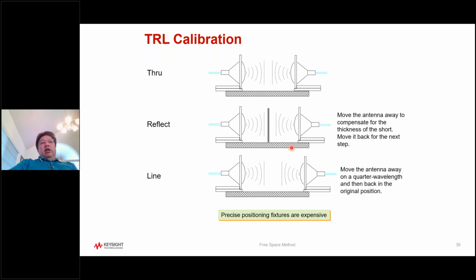It does require calibration. The TRL calibration is the best. The through, which is nothing there, then reflect: if you put the metal plate in the middle, you have to move the antenna back to be the same thickness as your metal plate. And then the line: you have to move an additional distance to accommodate the quarter wavelength as well as your plate.